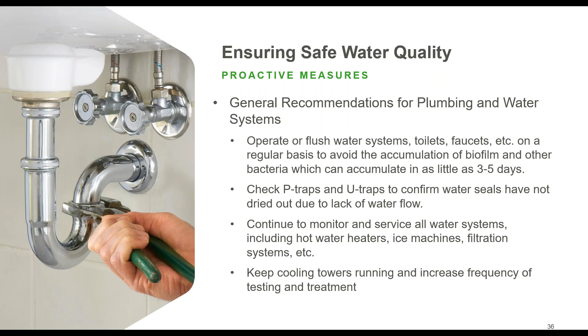Now, if you have cooling towers, ASHRAE recommends keeping these systems running so the equipment stays in its best shape. If the chilled water system has to be taken down for an extended period of time, completely drain the cooling towers, chillers, heat exchangers, and associated piping. Leaving the system with stagnant water can result in severe corrosion, biofouling, and contribute to the transmission of Legionnaires disease. Lastly, if operating at a reduced capacity for an extended duration, increase the frequency of testing and adjusting of the biological control regimen by your water treatment provider. So you can see that there is a lot to think about as it relates to the water systems in your buildings.